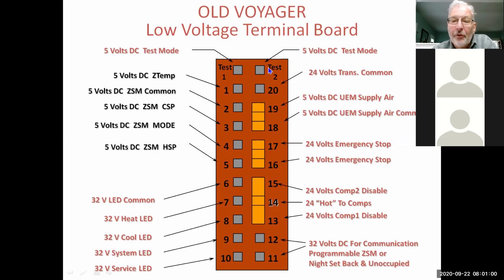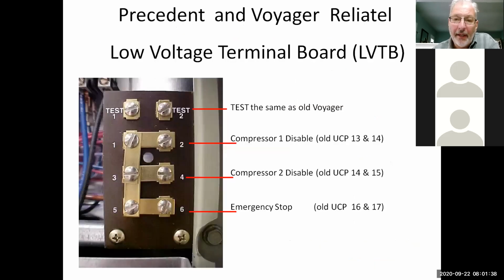Now, when you're on these units, you can isolate the economizer. On the old units, there's a 12-pin Molex up near the roof in the filter section. And on the new Modbus or the ReliaTel systems, you can actually unplug the Modbus right from the economizer module. Or sometimes you can unplug J4 on the ReliaTel board. You got to be kind of careful with the J4 because if it's a dehumidification unit, it will disable the options module and then the system won't run. So you got to kind of know what you got before you unplug the J4. But as far as test mode, again, it worked on the old as well as the new.